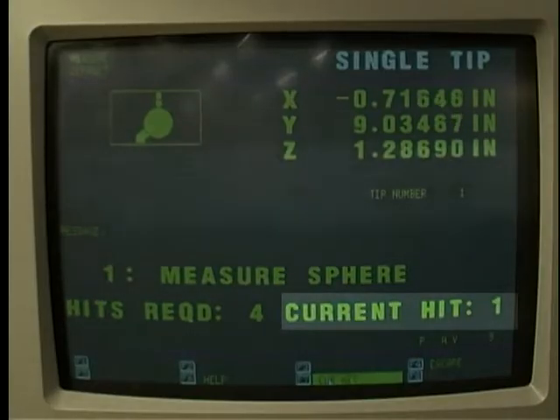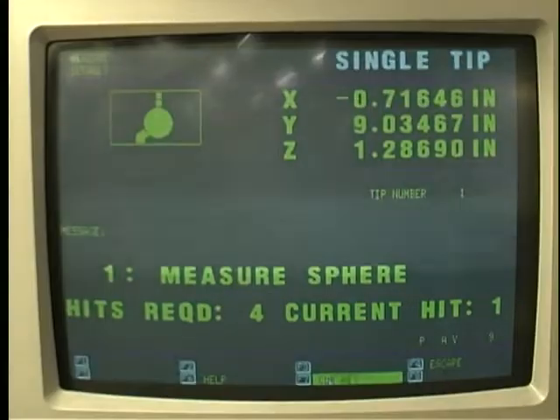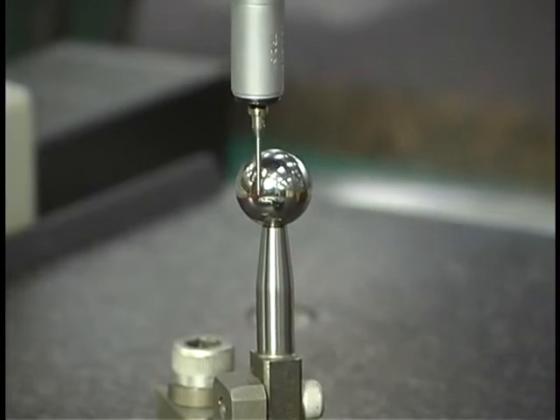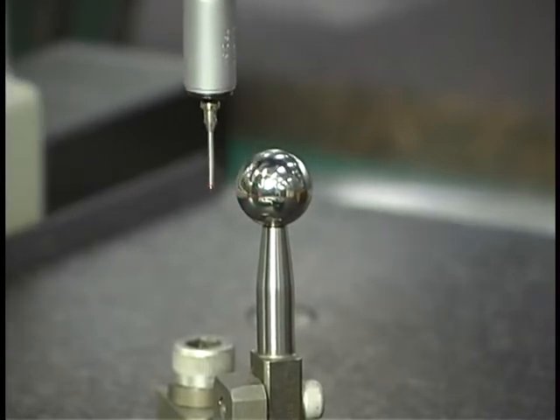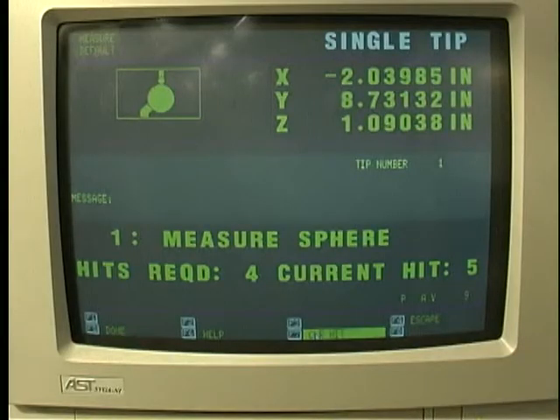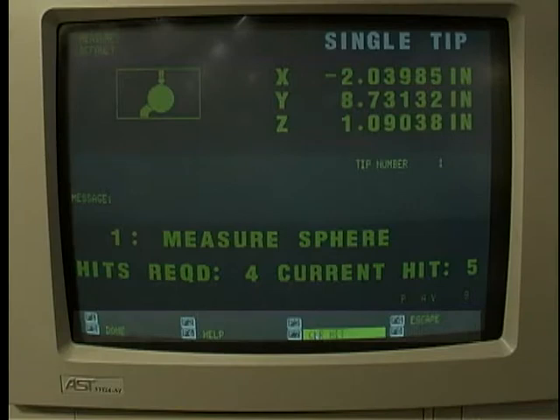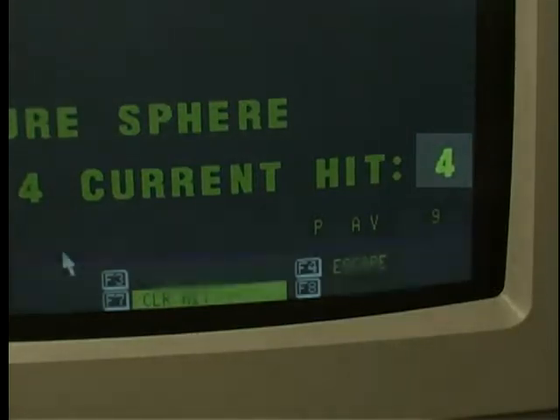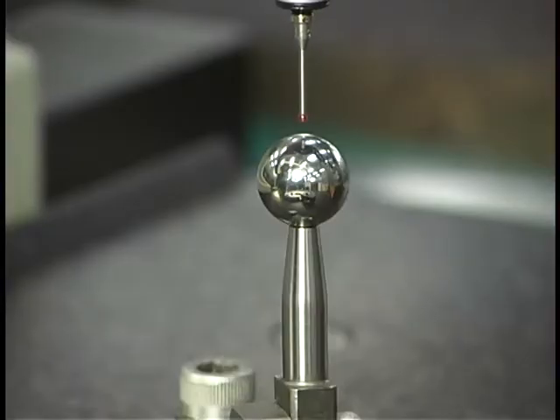On the computer screen, one hit has been registered. Additional hits are performed on the remaining three sides of the sphere using the same procedure. If a hit is made at a wrong location, it can be removed from the computer. At the bottom of the screen, a listing of other menu options is shown. Clicking on Clear Hit removes the last value entered into the computer.